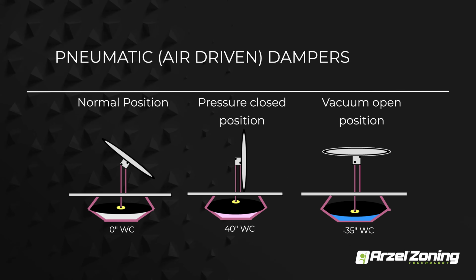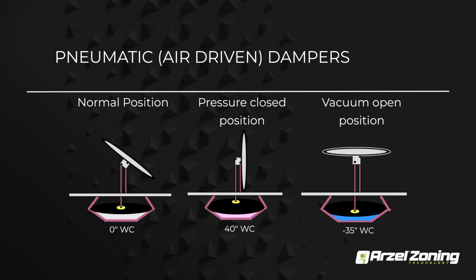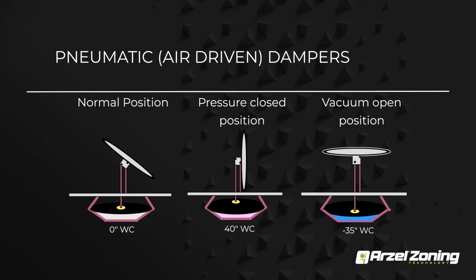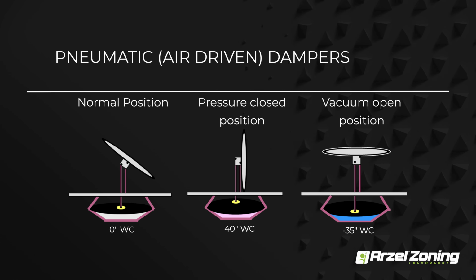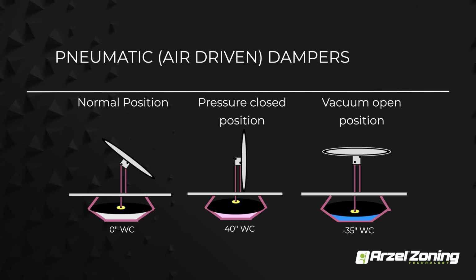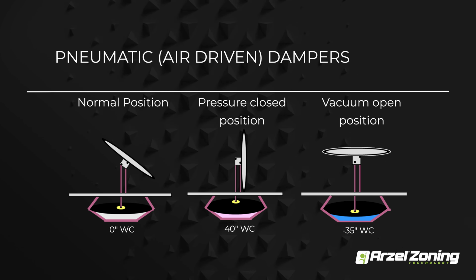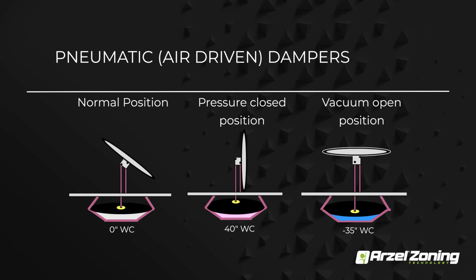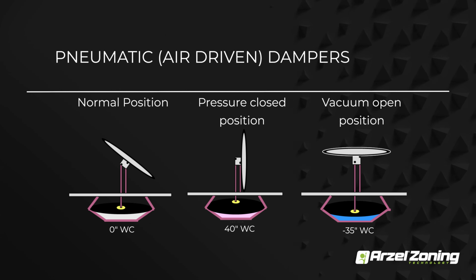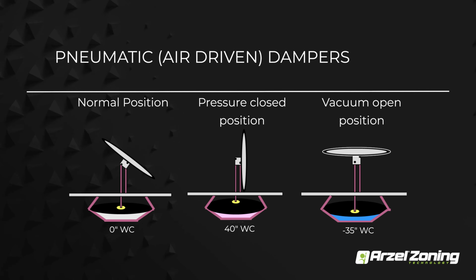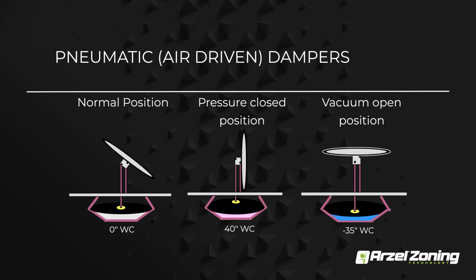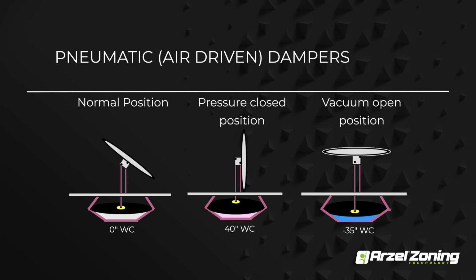As far as our dampers go, their normal position is about a 45-degree angle in the ductwork, so they are open in the ductwork. If you guys are doing humidifiers and you want blower activation, typically we recommend ignoring our panel completely. It'll blow through that whole system and humidify that whole home when there's no call on the panel, and then it'll just close the opposing zones when there is a call and continue to humidify only the areas that are calling. They are pressure closed and vacuum open, and our minimum operating pressures are -35 inches of water column to open and +40 to close.